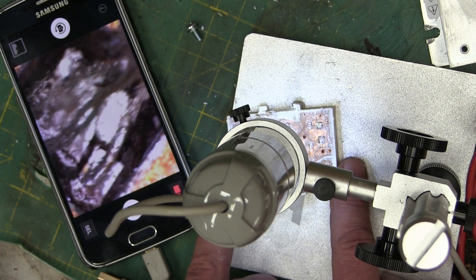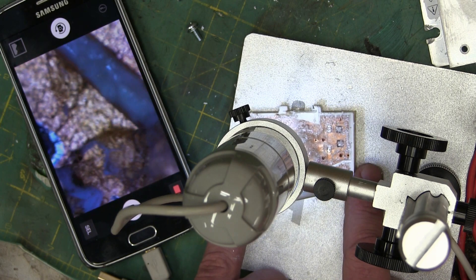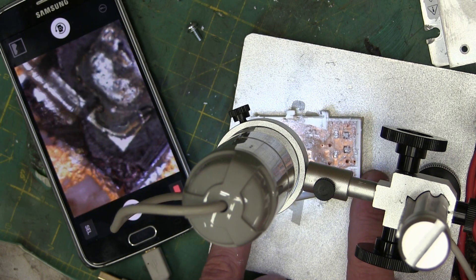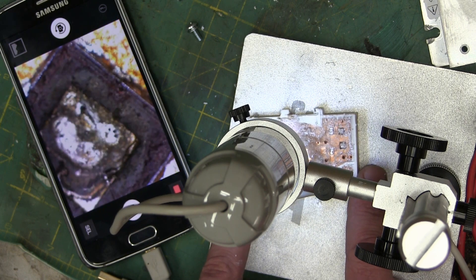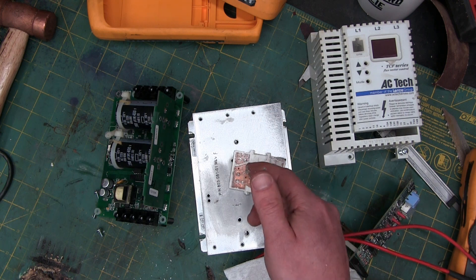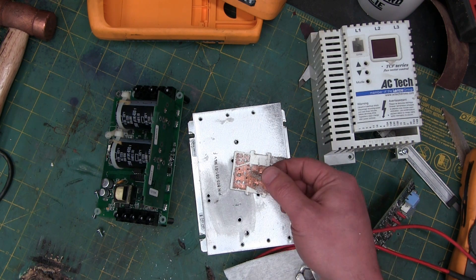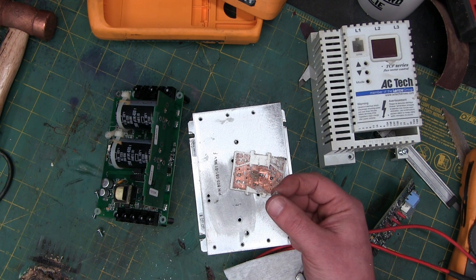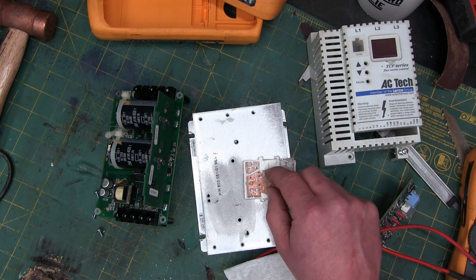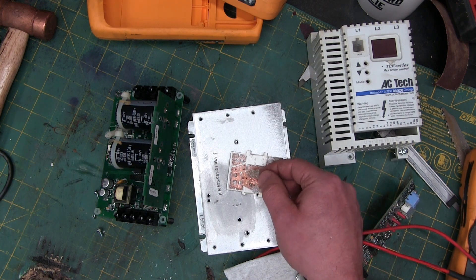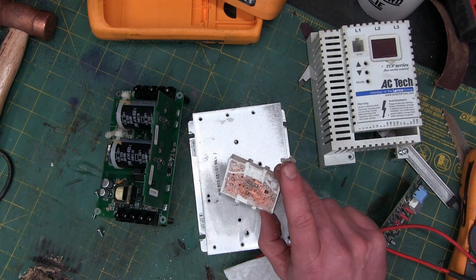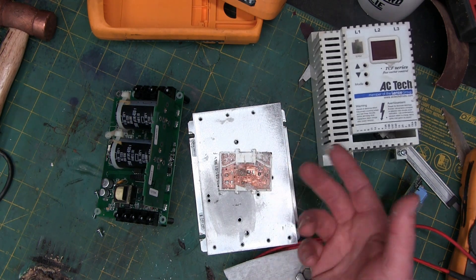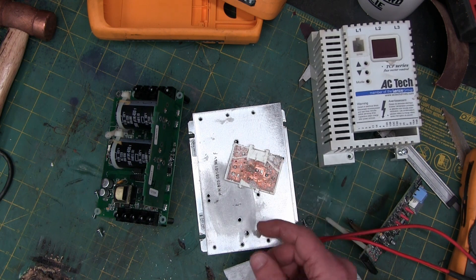So that is what fried. The IGBT itself fried, not the diodes, which would indicate just a general lifetime failure. Overheated. It got tired and gave up the ghost. The snot, what contains the smoke is just... I wonder how they make it so it never... it's always snot-like. Probably a pretty amazing material. Luckily, I'm not in California, so it won't give me cancer. That is what it looks like when doves cry and AC drives fry inside the life of a commodity part. It just gave up the ghost. It died of natural causes.